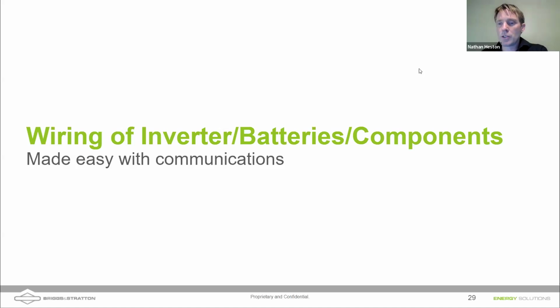Bill asks, you mentioned a Sol-Ark inverter will accept 100 amps of generator. Does all 100 amps pass through to the load, or is 50 amps to the load and the rest goes to the battery? It's 100 amps of pass through, and if the battery is in a charging cycle, you can get up to 275 amps DC of charging. So I think that's about 12 kilowatts worth of charging. So yes, you can pass it through to load, but you can also use that power to charge the batteries.